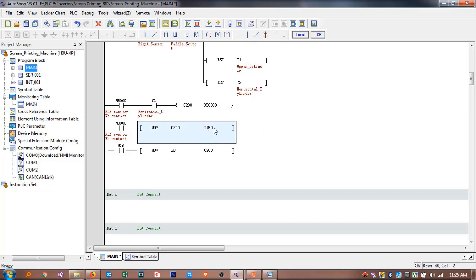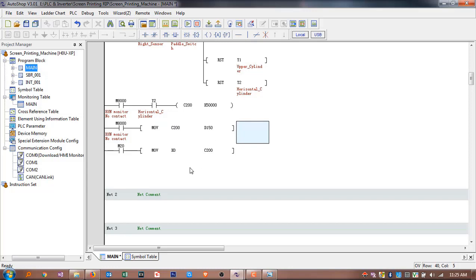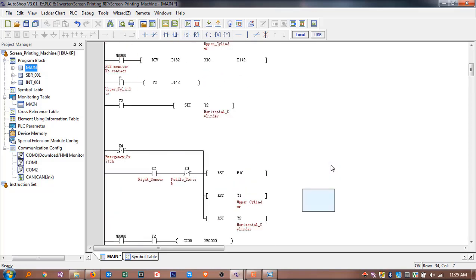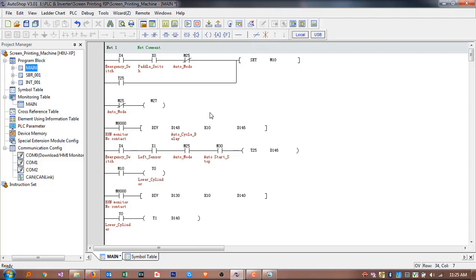We display d150 on the HMI because HMI cannot directly show a counter value — it must be a data register. When anyone presses m20 from the HMI, a MOV instruction moves 0 to c200, resetting the counter to zero so you can start counting a new production batch.